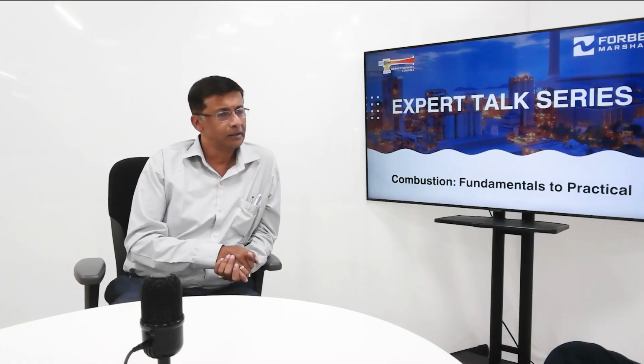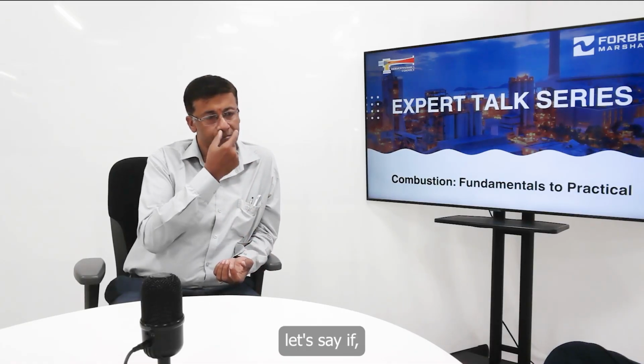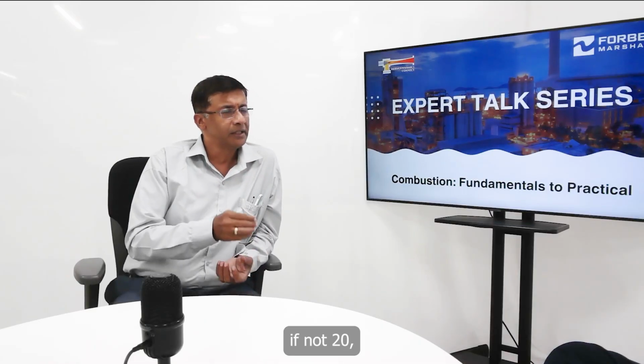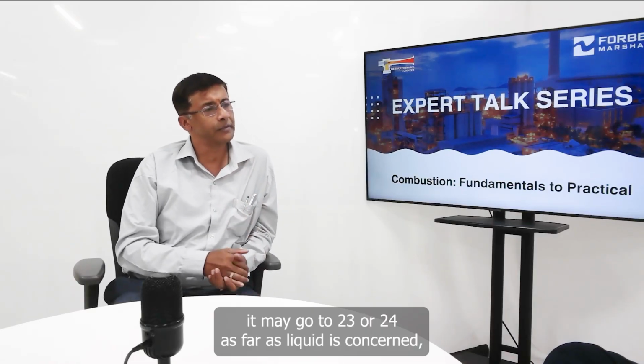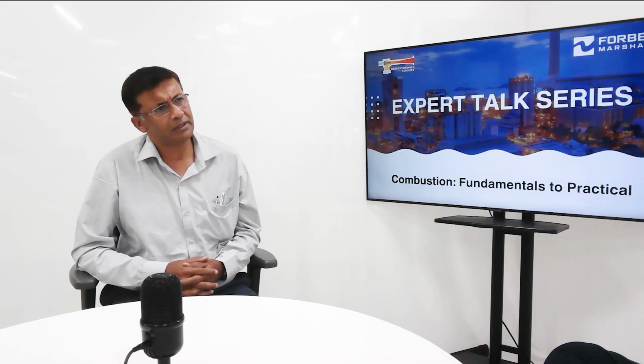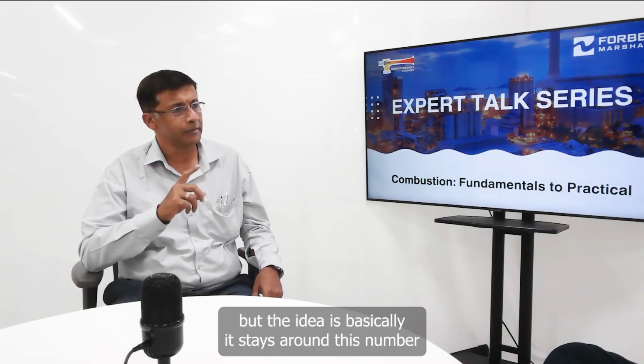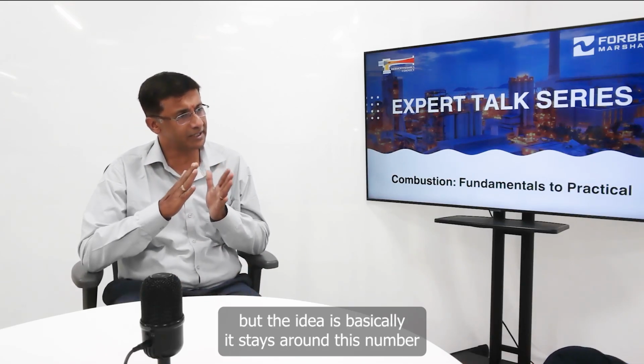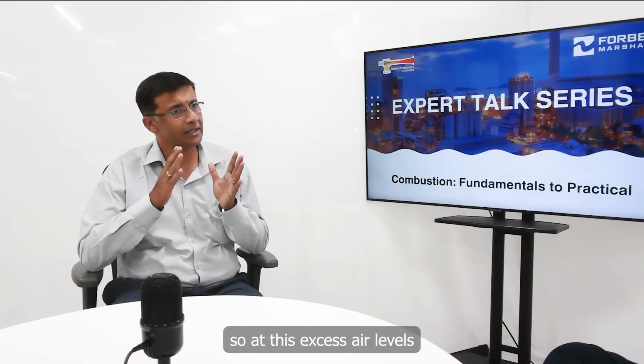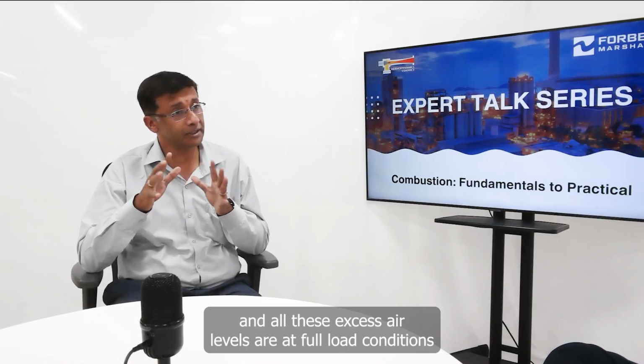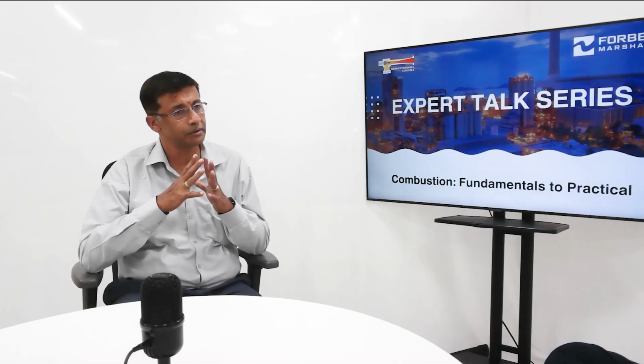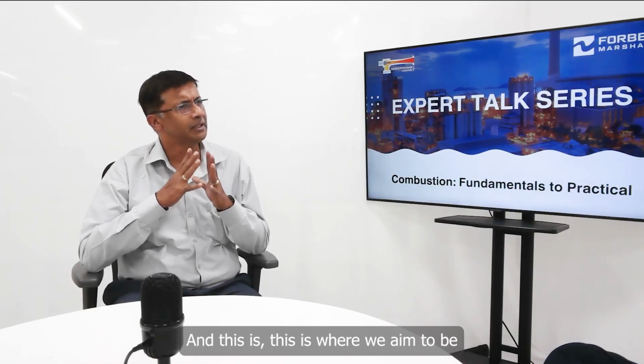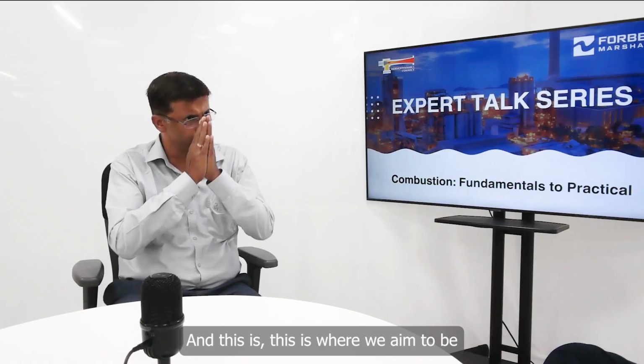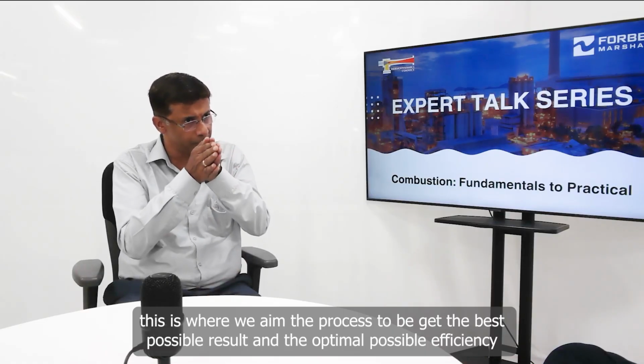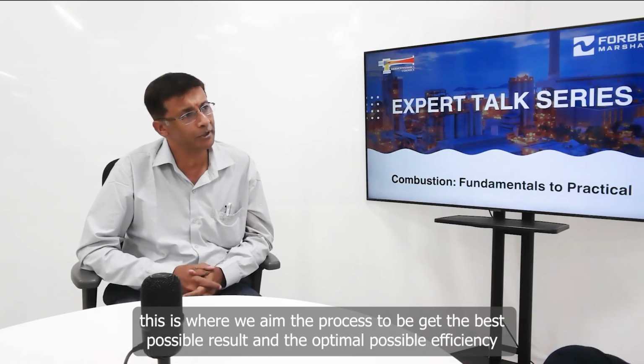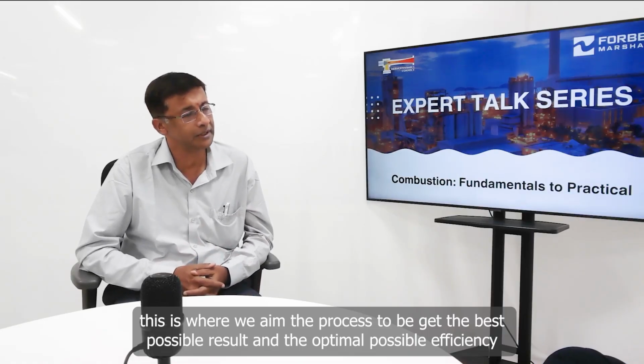So he is the one who determines what it is, and you can have a small change in the band. Let's say if not 20, it may go 23 or 24. As far as liquid and gas are concerned, the band is smaller. But the idea is basically it stays around this number. At these excess air levels, you get the best possible efficiency, and this is where we aim the process to be.